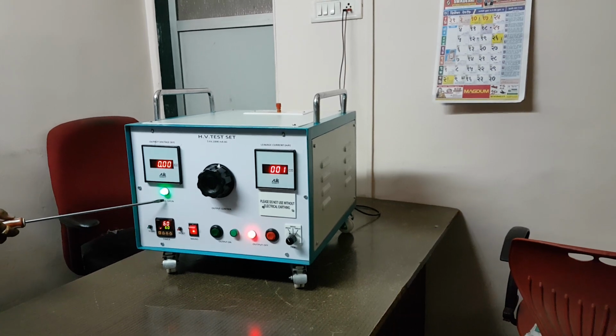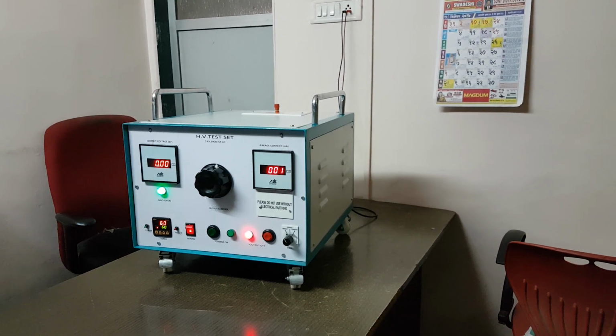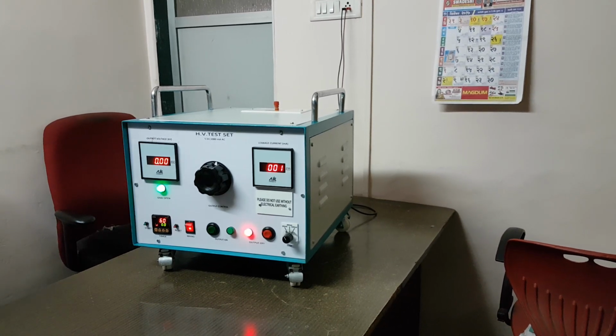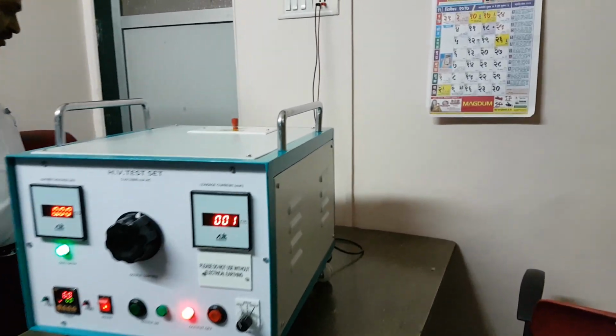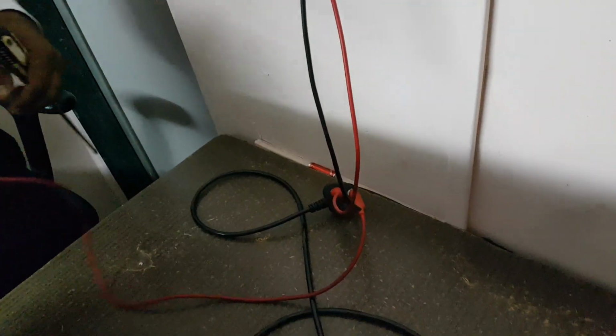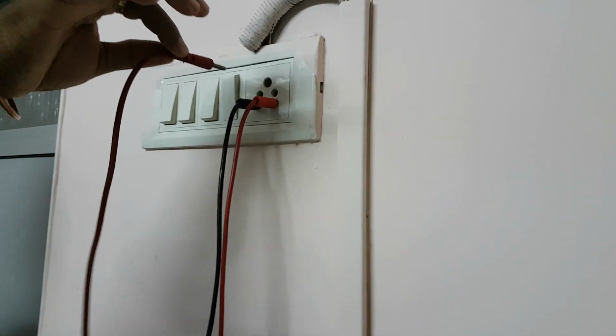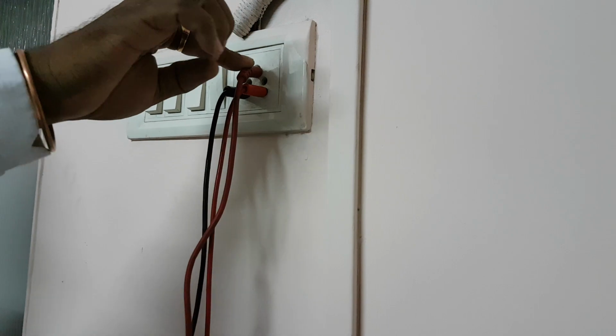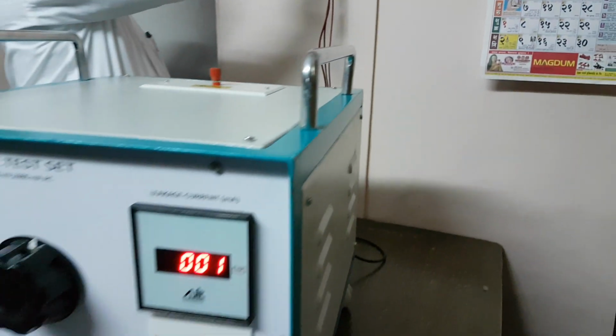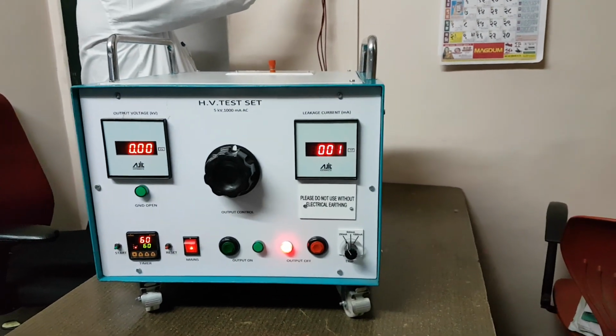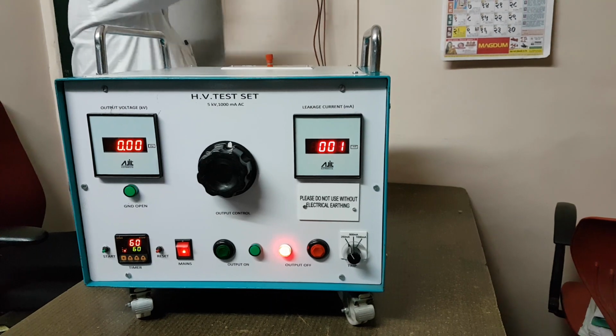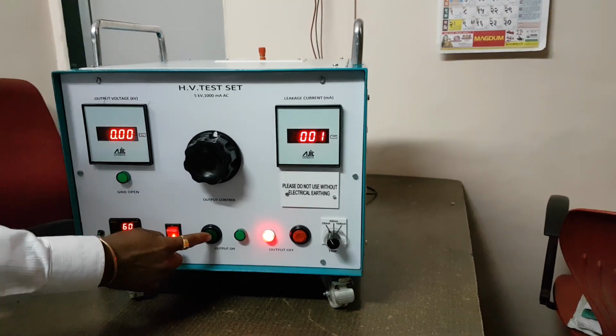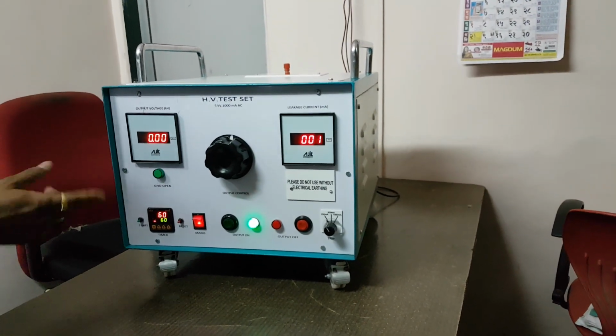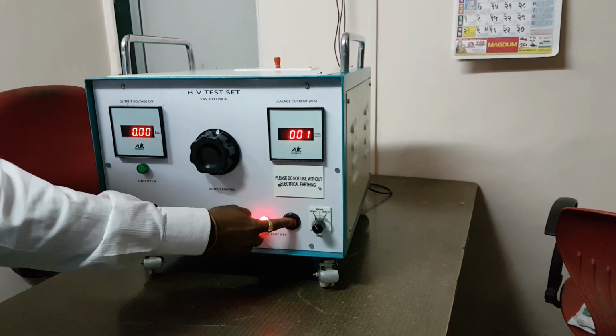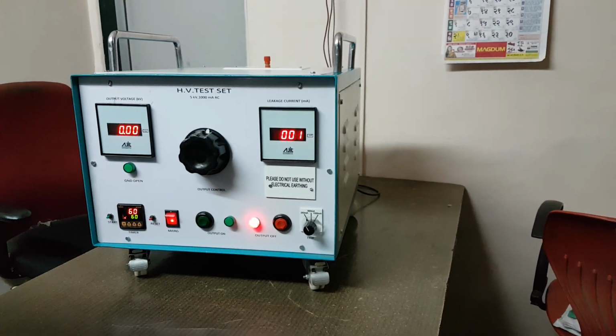So this interlock has operated and the instrument is asking to connect the earthing properly, and if I check, really the electrical ground is not connected here. It is not connected to the instrument. So now here is the connection, and now physically I will connect this ground here and see the indication on the instrument. The open ground indication has vanished, and so the instrument can be initiated for high voltage. So this is the open ground interlock facility in the instrument, which ensures the safety of the instrument as well as the safety of the operator.